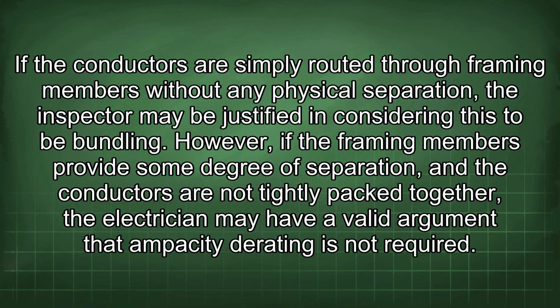If the conductors are simply routed through framing members without any physical separation, the inspector may be justified in considering this to be bundling. However, if the framing members provide some degree of separation and the conductors are not tightly packed together, the electrician may have a valid argument that ampacity derating is not required.